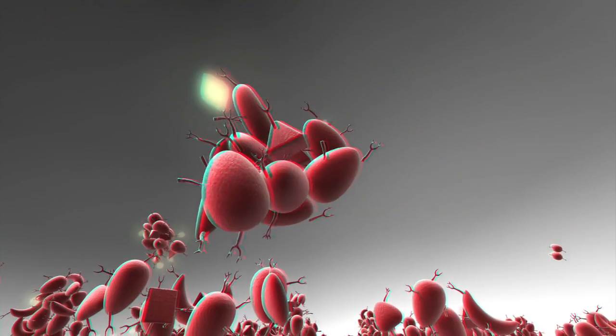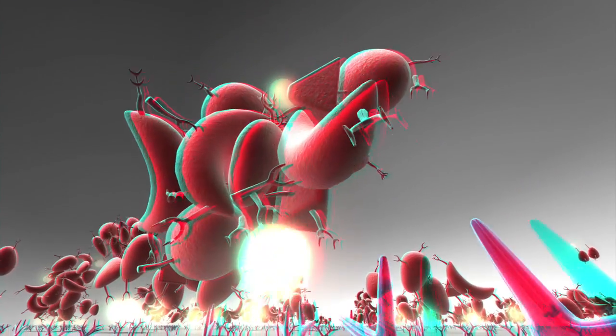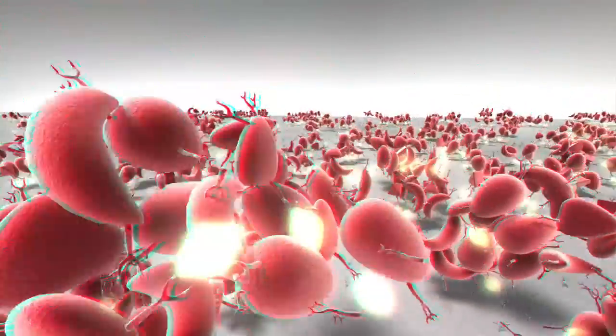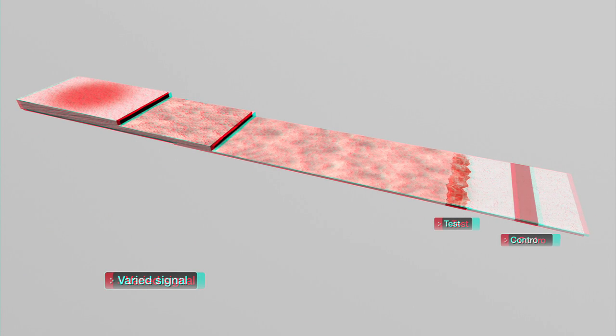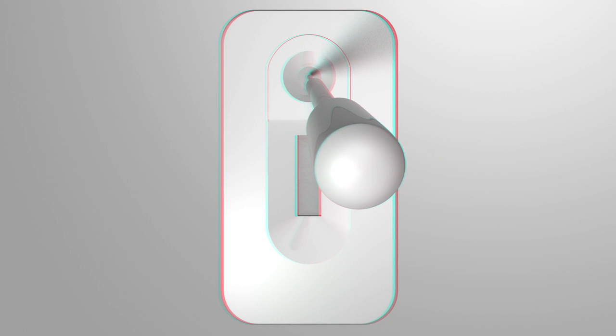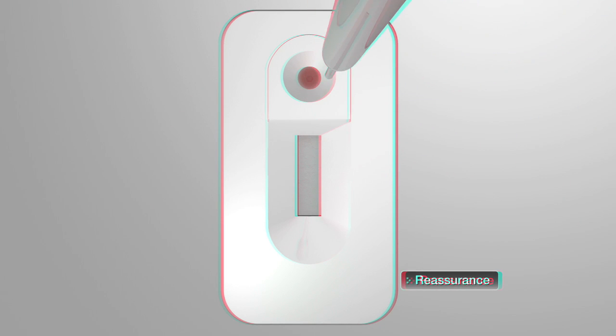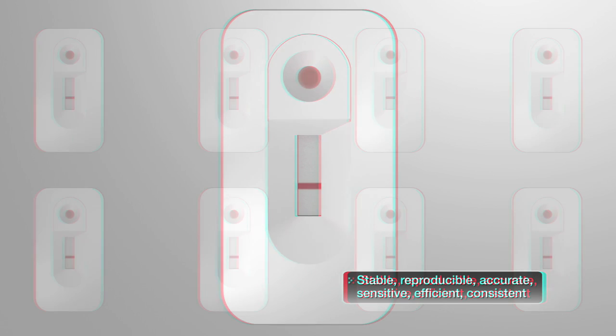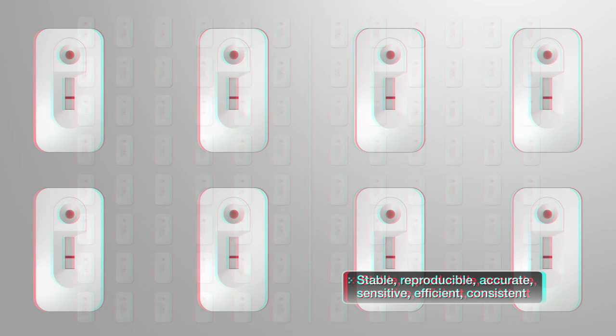With poor quality gold, the antibody does not attach cleanly to the antigen in the sample, weakening the intensity of the visual signal and increasing the likelihood of background staining. This can result in varied signal intensity, lacking definition, and possible edging, which is open to misinterpretation of the test result. Good quality gold guarantees consistent, reliable results for the entire cycle of the assay, long-term stability and shelf life, a smoother development process, and ease of transfer to full-scale manufacture.